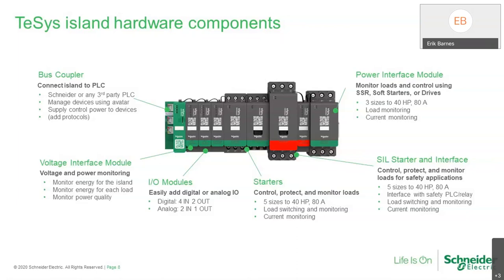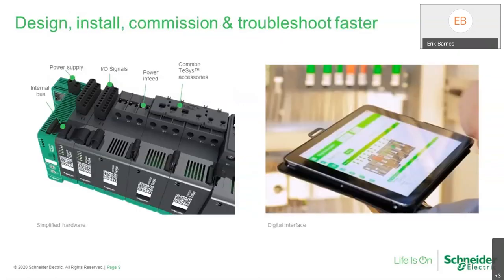And then we also have what's called a power interface module. This is similar to the starter, except it doesn't do the switching. It's only doing the monitoring, and you could use this in cases where maybe you want to use a soft starter. So you put the soft starter downstream of this power interface module. You still can monitor the units through this unit here through the island, and still be able to have the same types of controls. So these are the hardware components of TeSys Island.